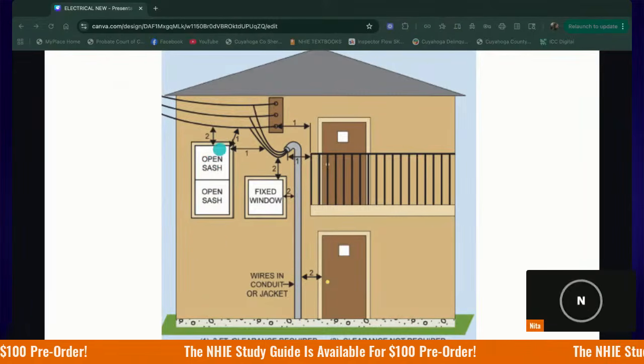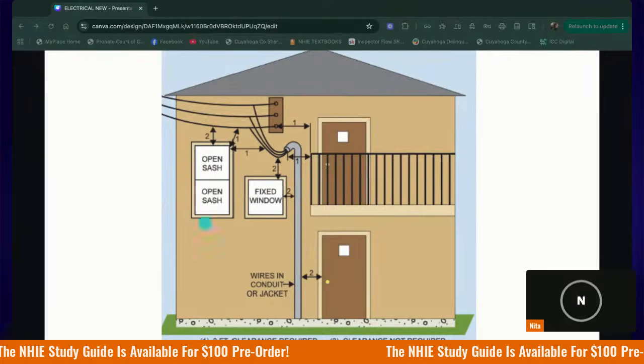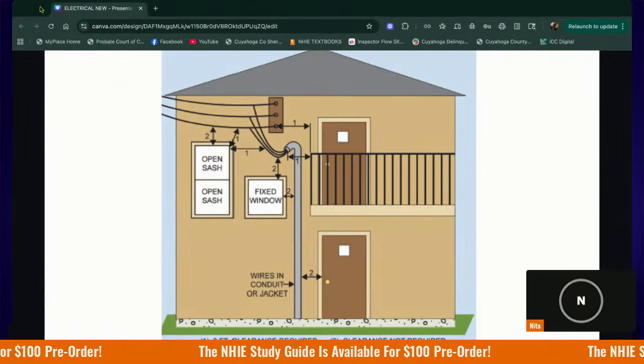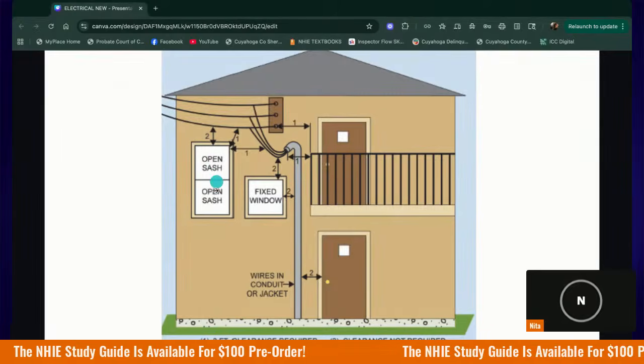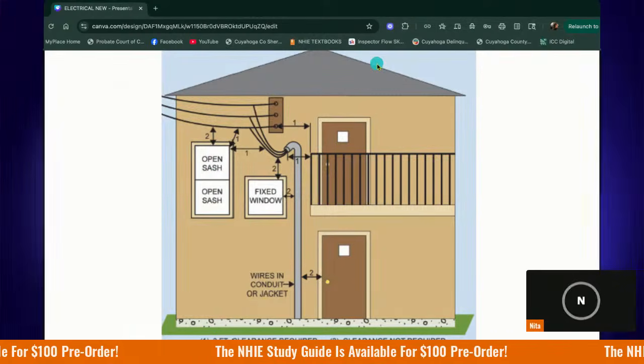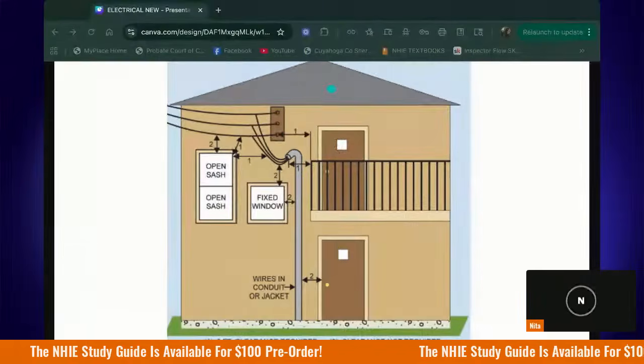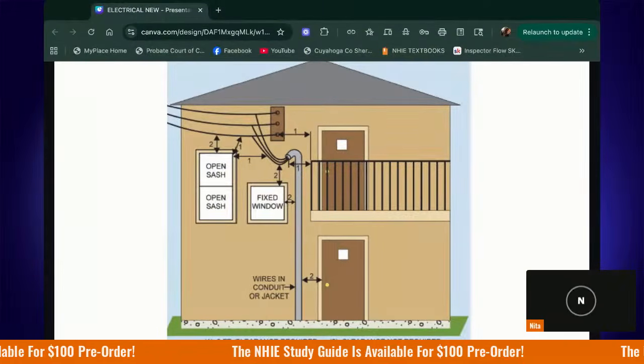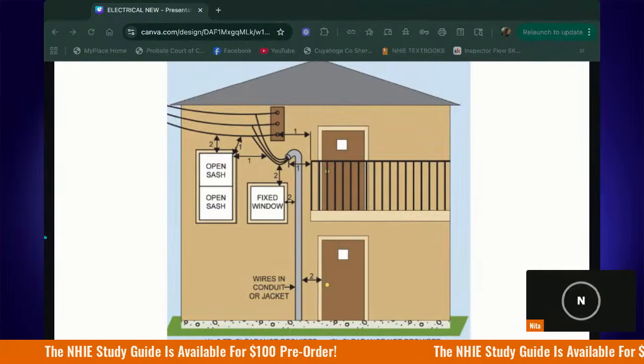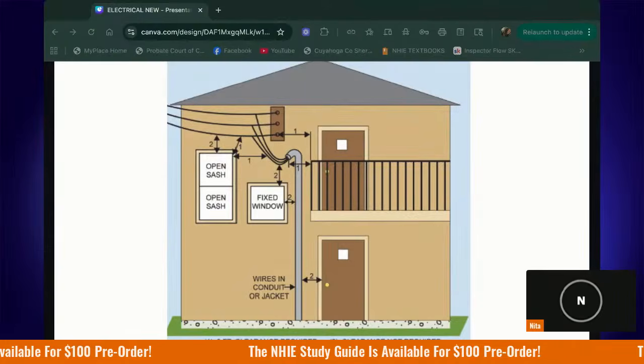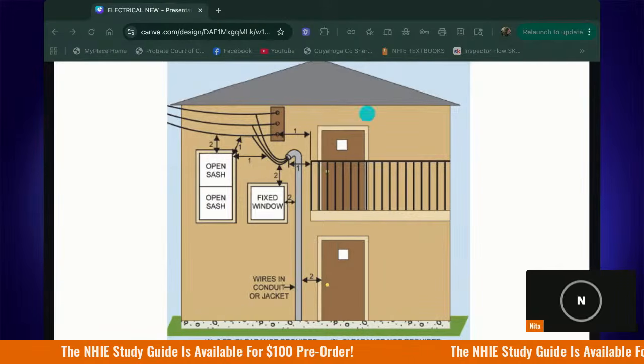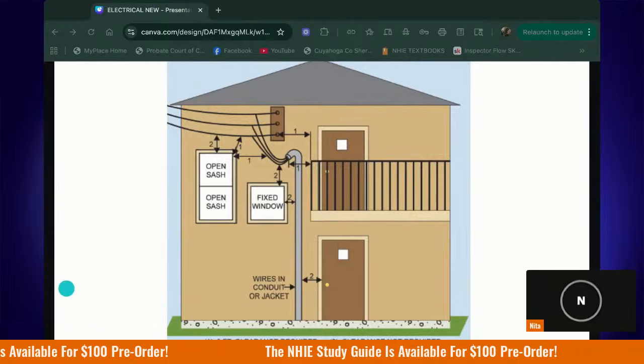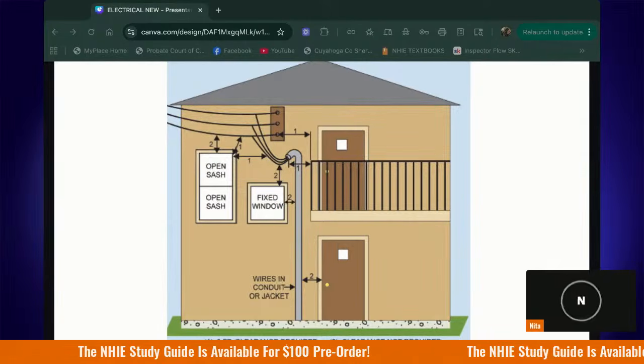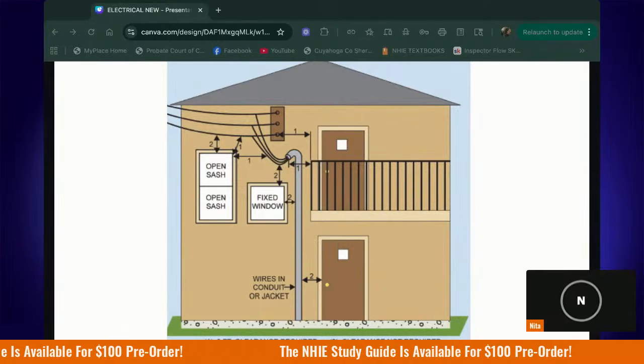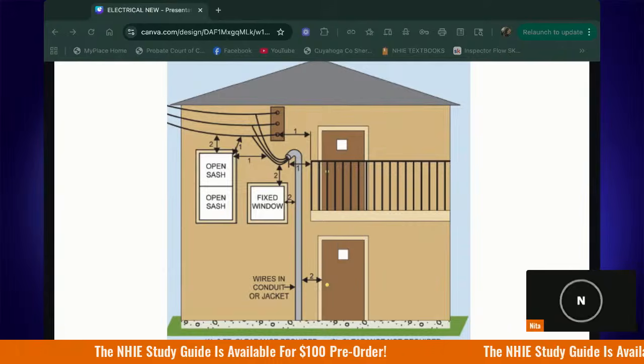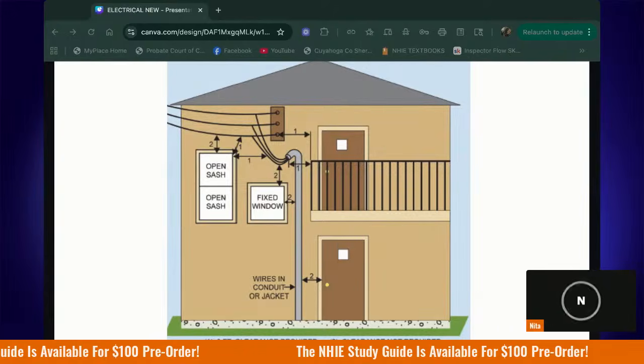So you see here, number one, 3 feet of clearance required, because these sashes open. It's an operable window. If you have a fixed window, then they can pass closer than the 3 feet. They just want them to be secured and actually not touching the surface. So that's number 2, where it says the clearance is not required because this is a fixed window. And then your clearance to doors is, again, you want to see 3 feet of horizontal clearance from any door or opening where a person could be in contact with the service drop.